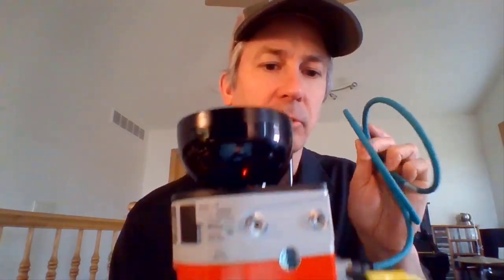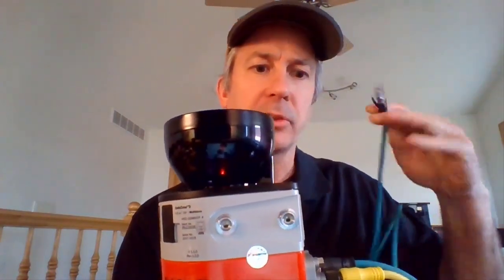The SafeZone 3 comes in the out-of-box configuration with no IP address. The easiest way that I find is to find a computer with BootP, or you can install BootP from our Rockwell website. Just take your cord to eliminate all network traffic and plug this directly into your computer.